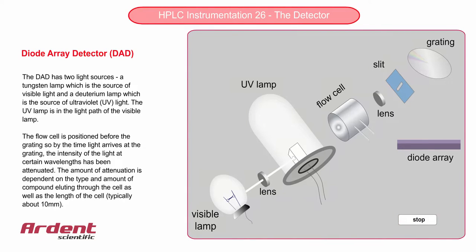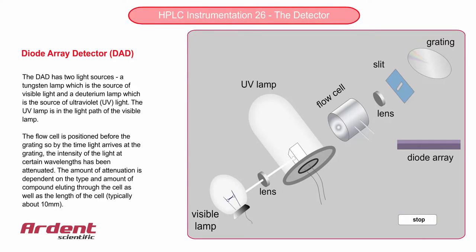The diode array is also a common detector, an advance on the variable UV detector. The difference with this type of detector is the flow cell is now located before the diffraction grating. Therefore, by the time the light has reached the grating, certain wavelengths of the light have already been absorbed by the component which is eluting through the cell. And these wavelengths will be dependent on the chemistry of the component itself.